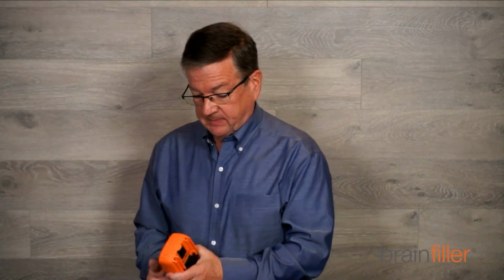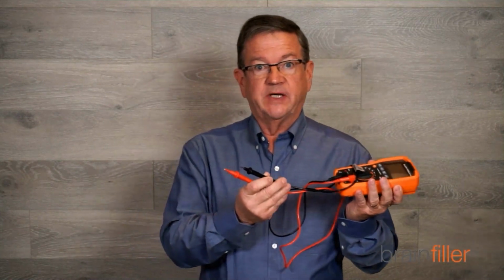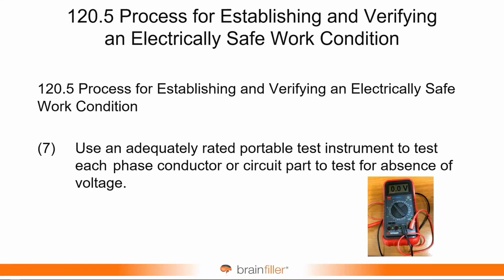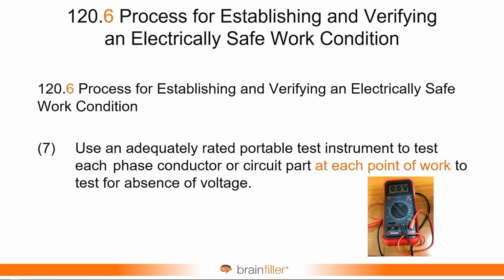It's a whole checklist. And one of the final steps in this checklist is to verify absence of voltage, typically using a portable test instrument. And so there was a bit of a clarification with this one. What happened is you use an adequately rated portable test instrument to test each phase conductor or circuit part to test for absence of voltage. That's what's already there. There was additional language that states at each point of work.